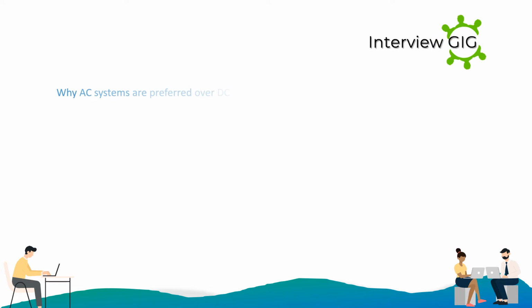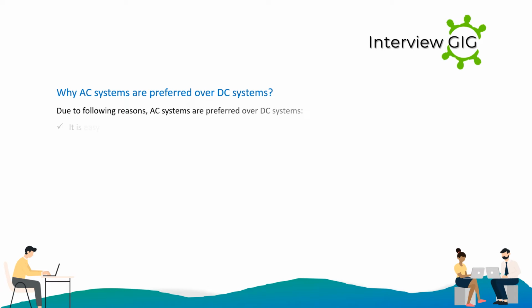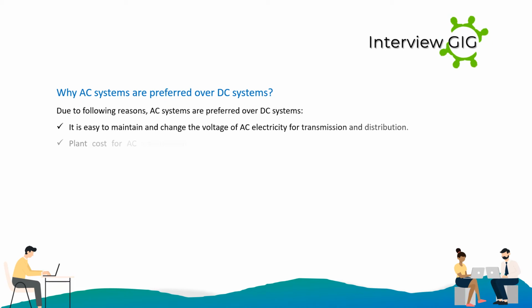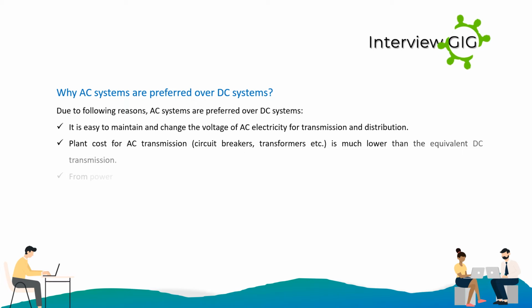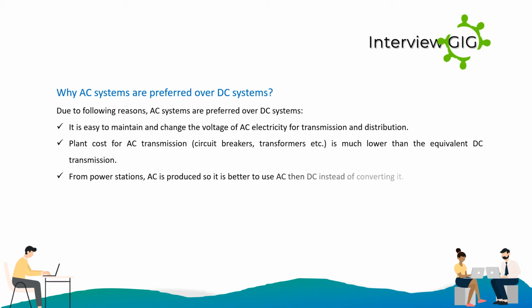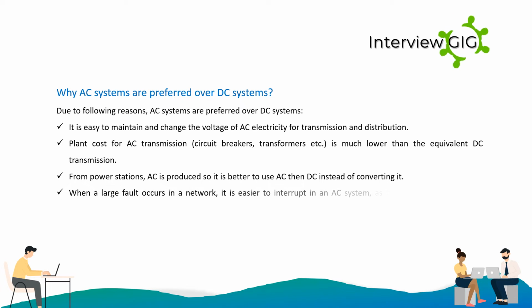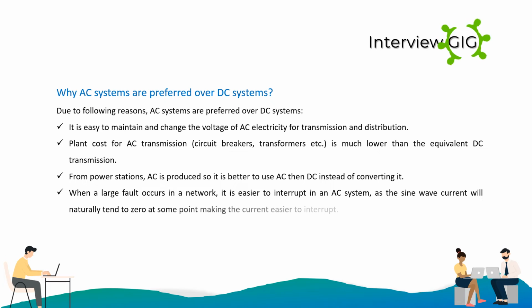Why are AC systems preferred over DC systems? Due to the following reasons, AC systems are preferred over DC systems. It is easy to maintain and change the voltage of AC electricity for transmission and distribution. Plant cost for AC transmission, circuit breakers, transformers etc., is much lower than the equivalent DC transmission. From power stations, AC is produced, so it is better to use AC than DC instead of converting it. When a large fault occurs in a network, it is easier to interrupt in an AC system, as the sine wave current will naturally tend to zero at some point, making the current easier to interrupt.